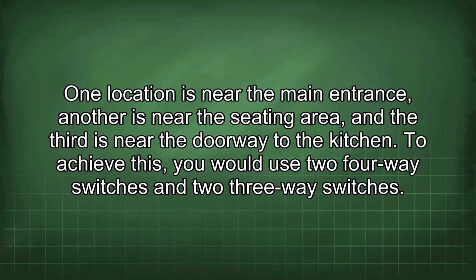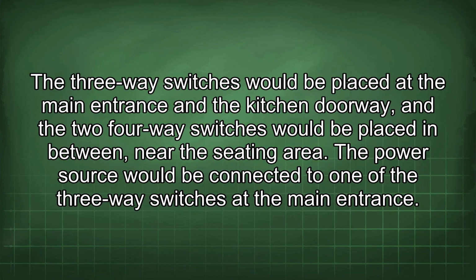One location is near the main entrance, another is near the seating area, and the third is near the doorway to the kitchen. To achieve this, you would use 2 4-way switches and 2 3-way switches. The 3-way switches would be placed at the main entrance and the kitchen doorway, and the 2 4-way switches would be placed in between, near the seating area.